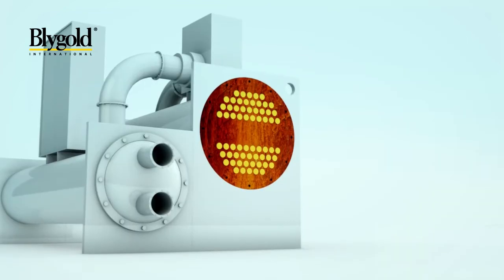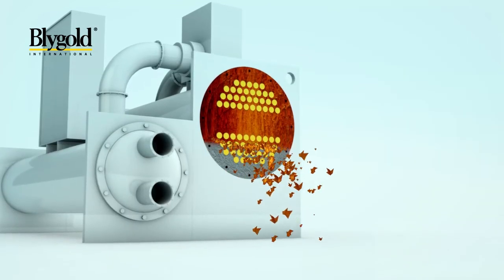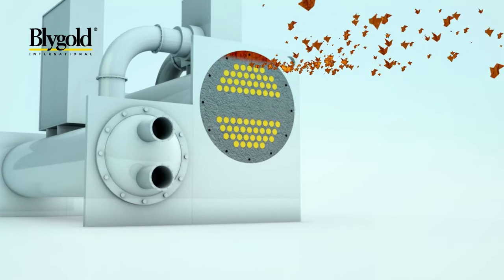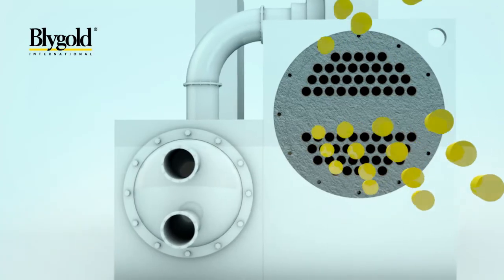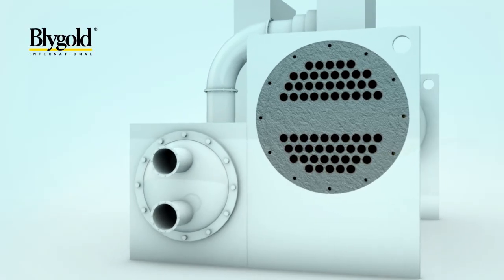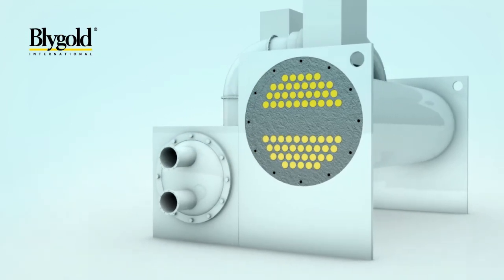After taking necessary measures to protect the tubes and the environment around the chiller, the target surfaces are blasted. The surface profile and cleanliness are checked and the tubes are plugged to prevent any material from entering them.